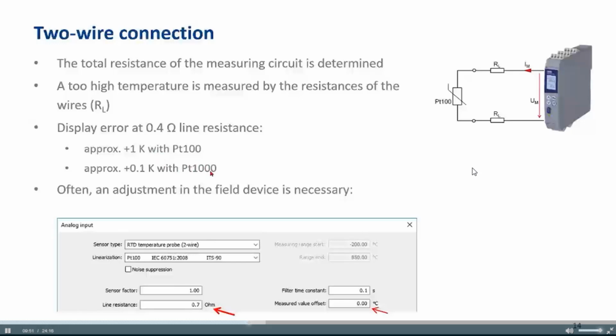If it's a PT1000, then with the PT1000 we have 4 ohms higher resistance with each Kelvin. On the other hand, this means if the line resistance is 0.4 ohms, then the offset is only 0.1 Kelvin. This is not so hard. But I think you can imagine very fast you can have a few ohms here, and then you have a few Kelvin higher temperature display.